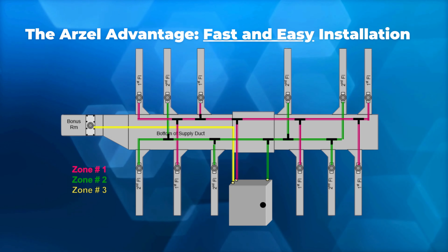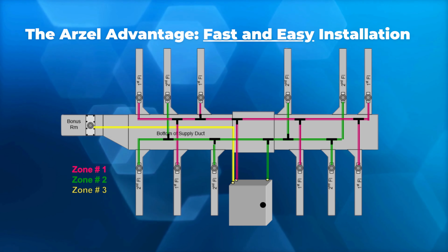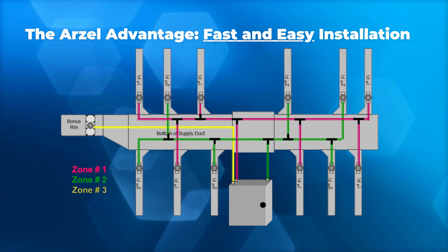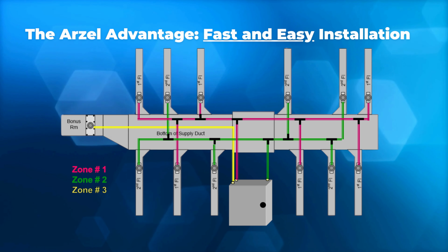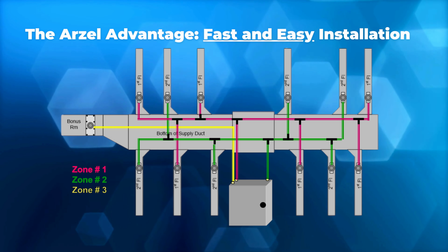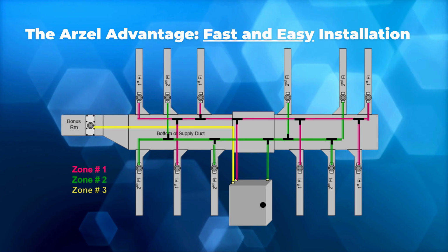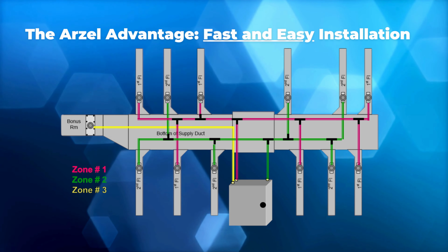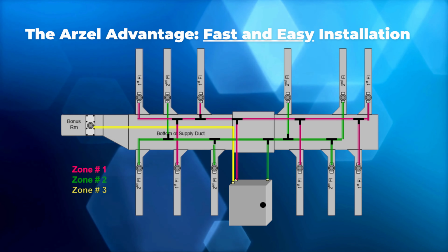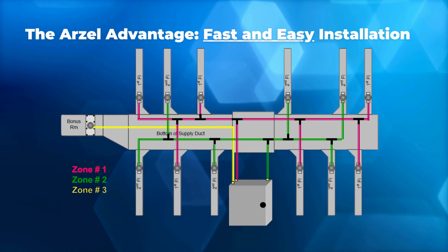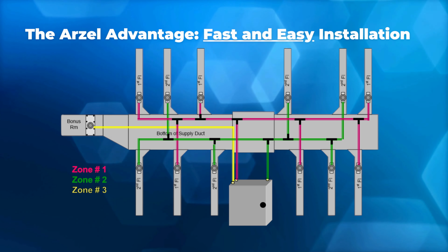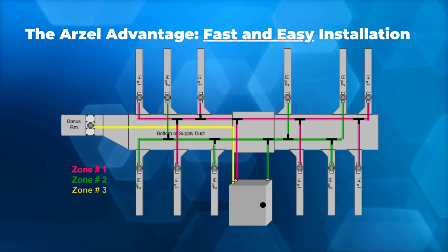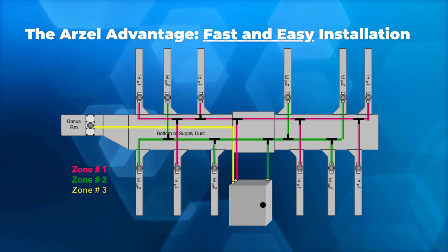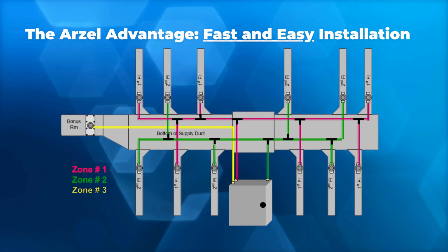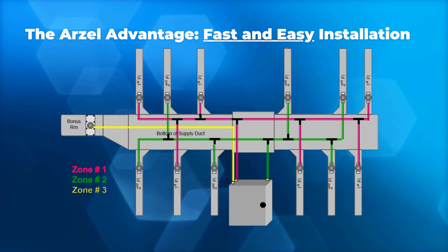Typically when you're running the tubing, you're going to want to leave the panel with your tubing and go to the furthest damper on that run. So you plug your tubing into that furthest damper, and then from there you're going to work your way back and essentially cut the tubing, install the T, and then connect the next damper in line. And you're just going to work your way back to the panel with the T's. So it makes it really quick. No wiring, nothing like that. So it's a really quick install time. And once you get all your T's done, that's pretty much what your finalized product will look like.